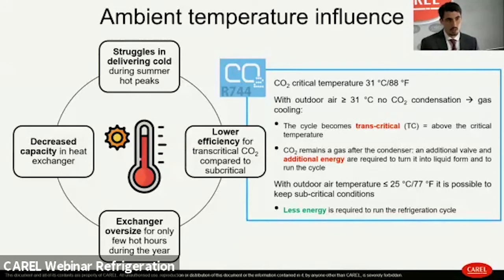So what are the effects? There is a decreased capacity in the heat exchangers. They are not enough anymore to deliver the capacity they were designed for. Also, there are some summer peaks where the heat is too much, and again it's a matter of not delivering the cold to cold rooms or cabinets and so on. Especially in food retail, this is quite problematic because it is mission critical to keep the goods at the correct temperature. Otherwise, there will be a loss of goods.